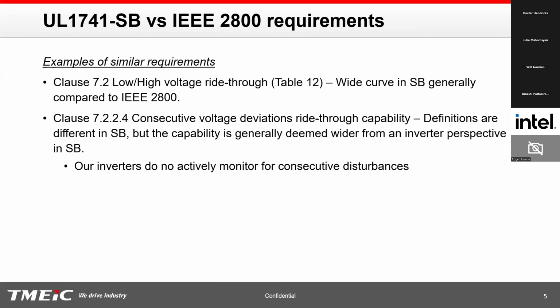Other similar requirements, we have voltage ride-through curves. In general, the ride-through curve is slightly wider in SB for most ride-through scenarios, but certain portions of the curve are wider in 2800. But we generally think that our 1741 SB inverter would be able to meet the requirements in 2800 as well. Similar thing with consecutive voltage ride-through. The ride-through specification in 2800 talks about a certain number of events per certain time durations, whereas SB has a very different definition of consecutive ride-through. But based on our understanding, we think that the SB requirement is probably a little more stringent than the 2800 requirement. Also, our inverters are not actively monitored for consecutive disturbances. So we believe that we would be able to meet that portion as well with the SB certified inverter.